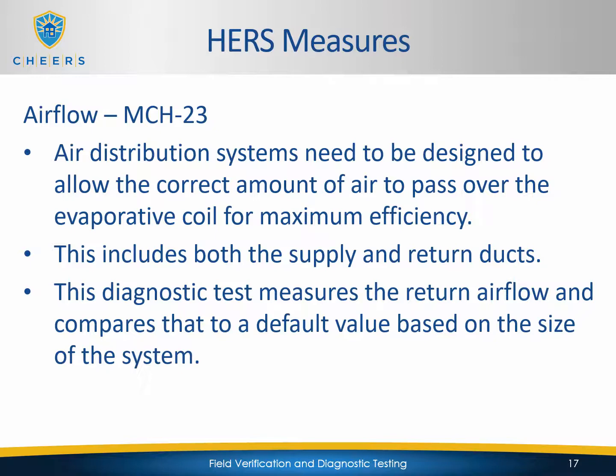So this diagnostic test measures the return airflow and compares that to a default value based on the size of the system. So not only do we measure the fan watt draw to see how hard the fan is working, we also measure the airflow to ensure that the return duct, at the size that it is and with the fan working as hard as it is, is moving enough air across the evaporative coil so that the cooling system can achieve its maximum efficiency. If we don't have enough air moving across it, it's going to cycle on and off more, and it's not going to be efficient like we need it to be.